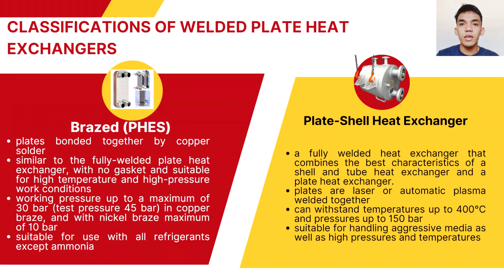This heat exchanger was designed and manufactured to meet the specific needs of the customer. It can withstand temperatures up to 400 degrees and pressures up to 150 bar, and works with liquids, gases, and the transitional phases between the two. It is welded together by a laser or automatic plasma. So, it combines the benefits of plate and tube heat exchangers, making it more widely used in the heat exchange industry.